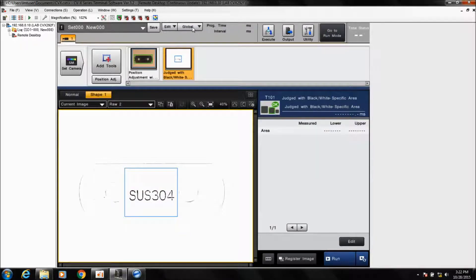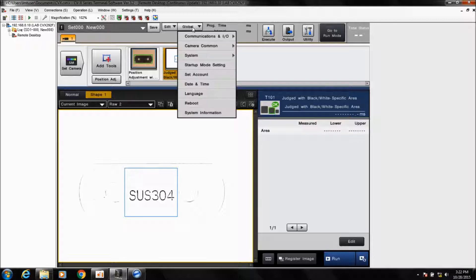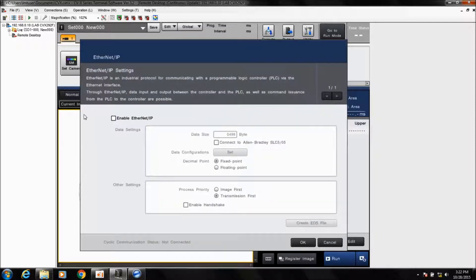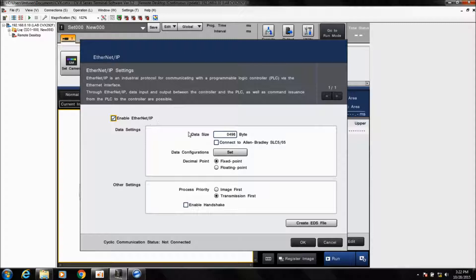To enable the Ethernet IP settings, you need to go into the global menu, Communications IO, and Ethernet IP. Simply check the box to enable the Ethernet IP setting, and this will enable the communication. The data size is automatically set — you normally don't need to change this, but you can lower it or set a different size if needed.